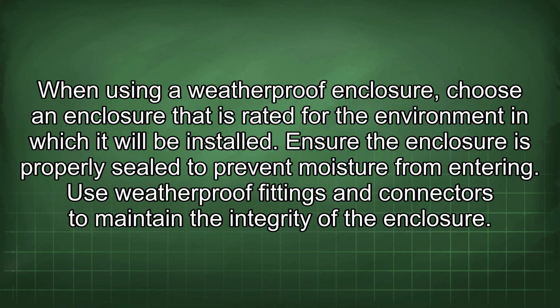When using a weatherproof enclosure, choose an enclosure that is rated for the environment in which it will be installed. Ensure the enclosure is properly sealed to prevent moisture from entering. Use weatherproof fittings and connectors to maintain the integrity of the enclosure.